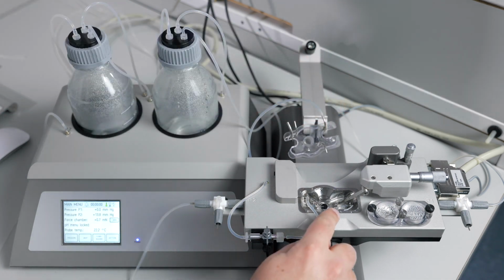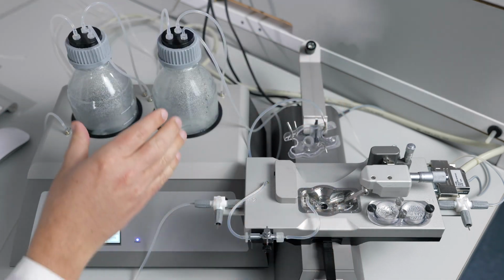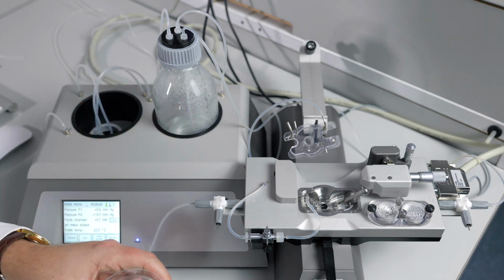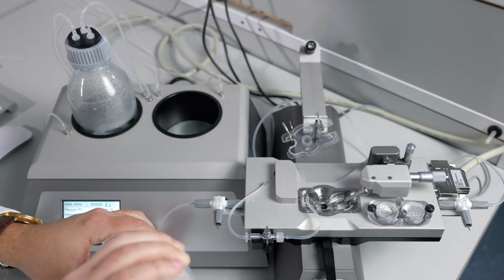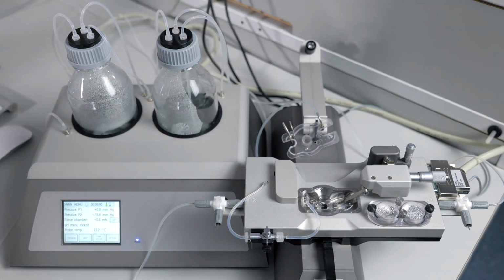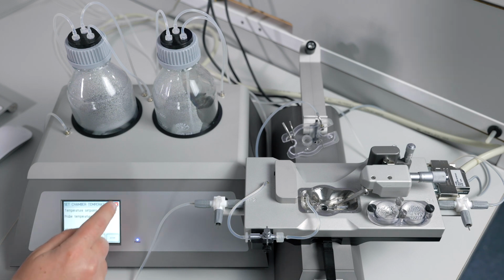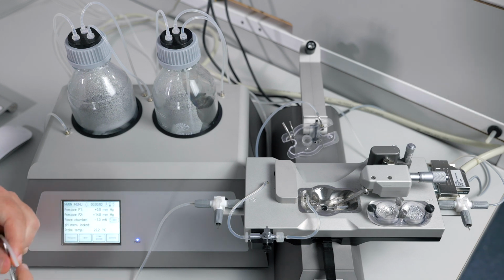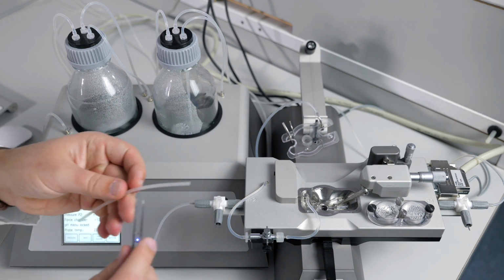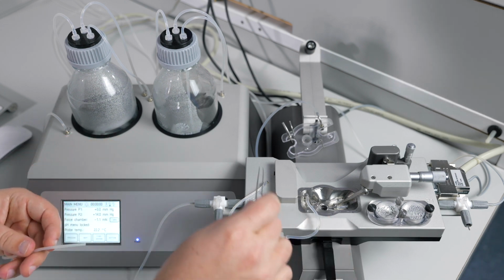We will also need to remove all the buffer from our tissue chamber and all buffer in P1 and P2 bottles. You will then turn off heat on the interface or using the MyoVIEW, and you will also place the calibration shunt bypassing the cannulas.